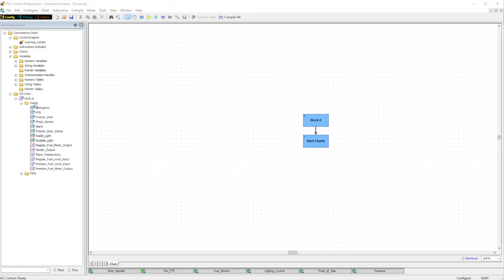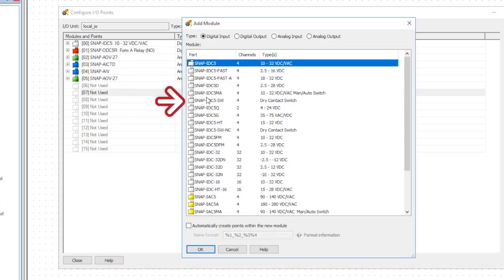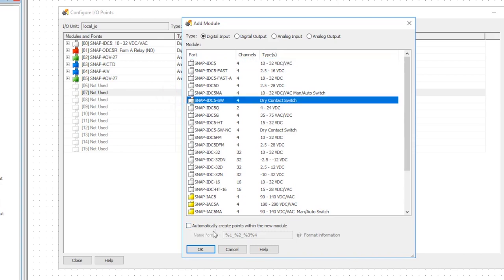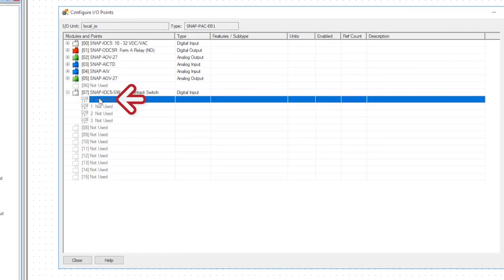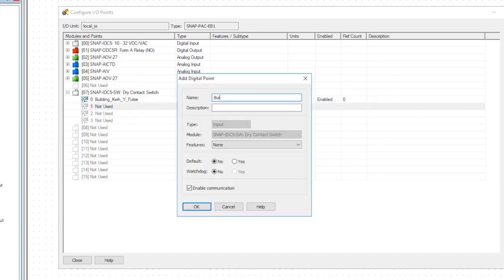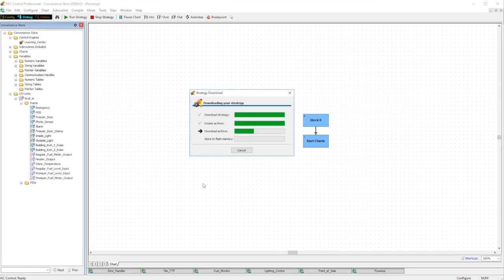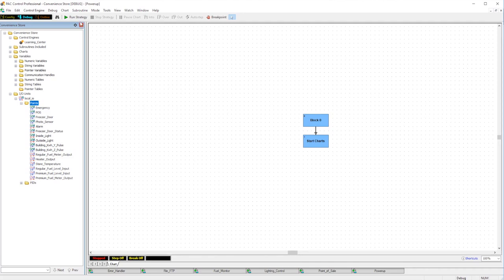Here we are in PAC Control. We've already got our I/O rack configured, so let's double-click on the empty slot in position seven to add our digital input module, the SNAP IDC5SW. Double-click on the first point of the module to open the point configuration dialog. We'll give it a tag name like "building_kwh_y_pulse" — this is where each input gets a meaningful name for your software application or cloud service, so choose your name accordingly. Let's double-click on channel two and call it "building_kwh_z_pulse." Now click the debug button to download the configuration to your controller, click yes to save, confirm the change, and the download process will start. Once it's done, click Run to execute the new strategy.